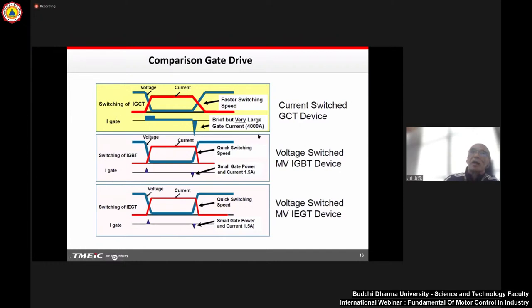This is one of the disadvantages of a GCT device, because to inject several thousand amperes into the device we need to make a very special gate circuit for switching. While IGBT and IEGT are not like this - you just need to apply the potential voltage, positive voltage for turning on and negative voltage for turning off. No need to put such high current to turn off. This is a major difference between the GCT device and IGBT or IEGT device.